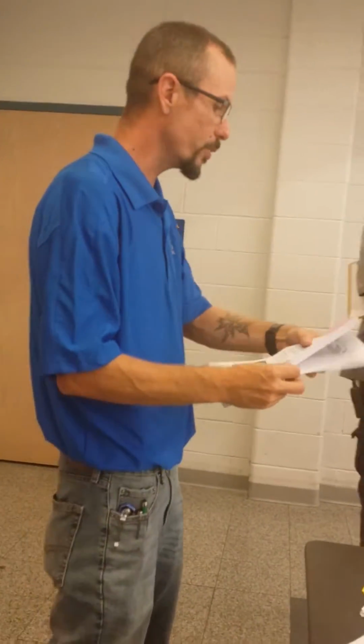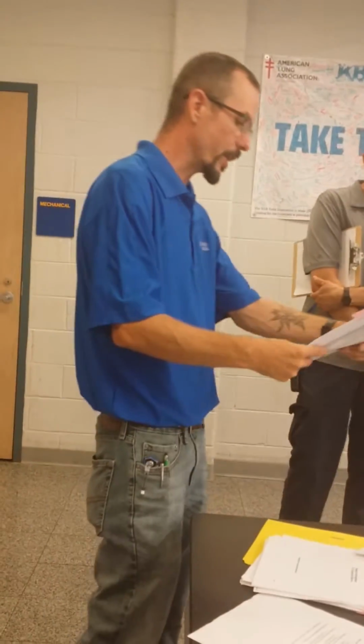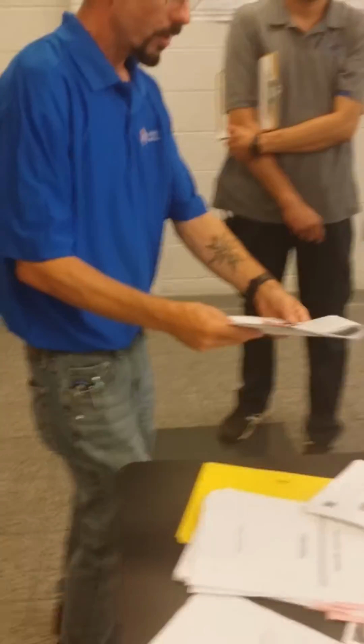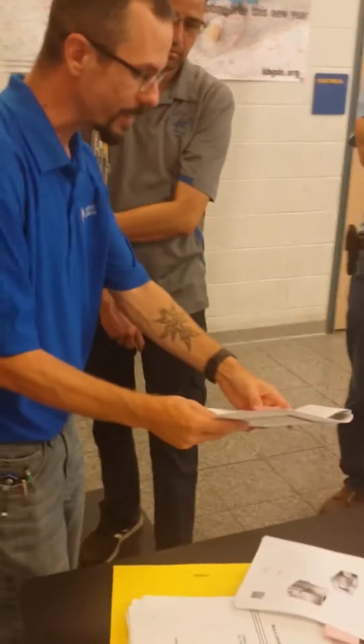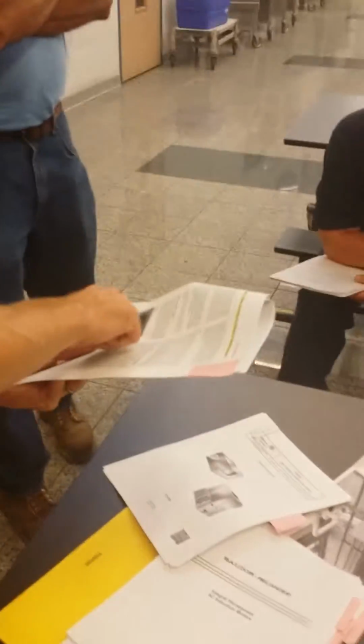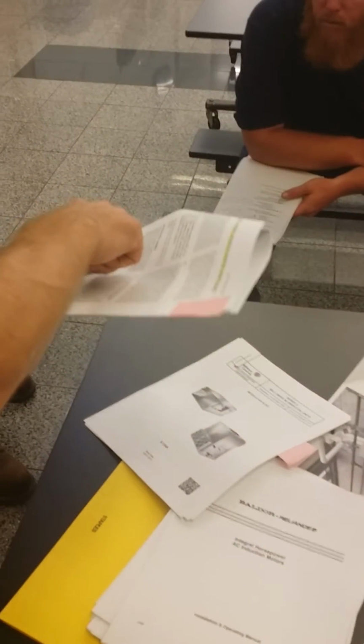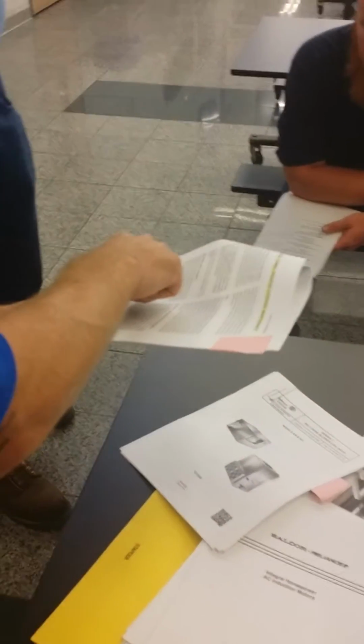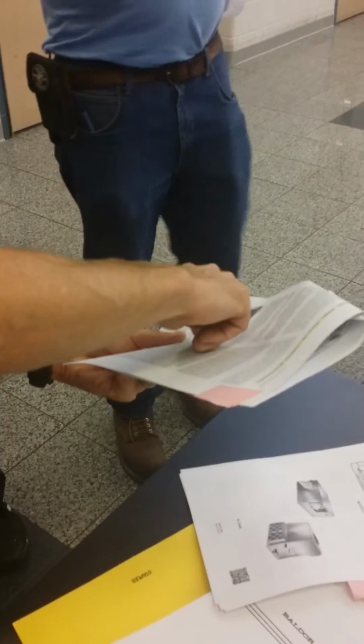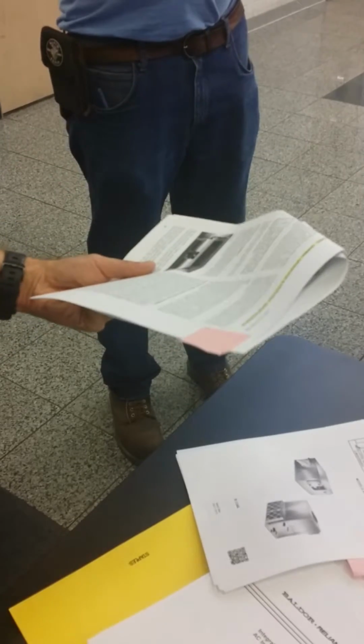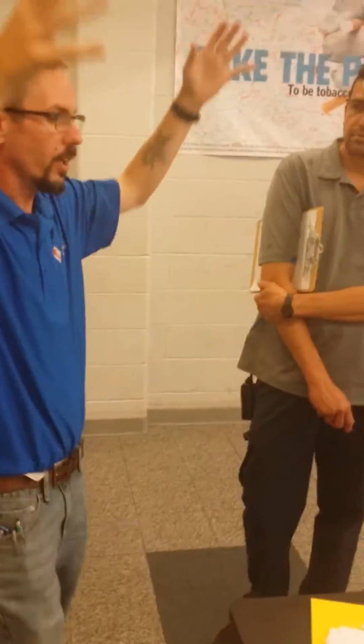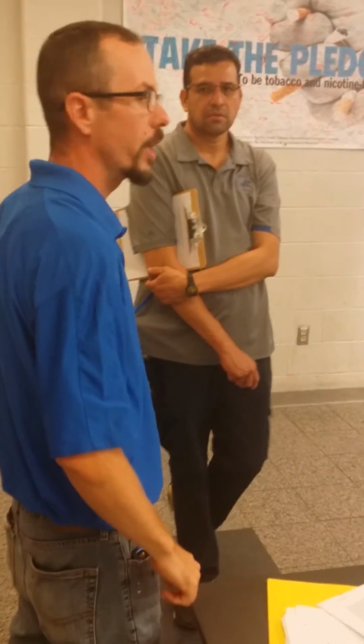The manual is going to dictate your normal and periodic maintenance of this. So if we look at the picture right here, because we're not accessing one, the motor is in between your 2 blower assemblies. They're ungodly to change, and you can only do it if you've removed the entire assembly. There are 2 screws right here and 2 screws right there. 4 screws will drop that down, and it's sitting up on a little clip on this outside side. So it folds down and drops down to you like a hinge. That way, it's going to take 2 men to get these out. Don't try to do it yourself.